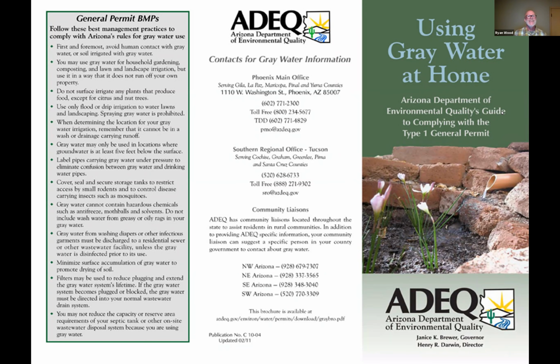So definitely, gray water may only be used in locations where groundwater is at least 5 feet below the surface. So here in the metro area, that's not a problem as far as the water table, but definitely out in the Buckeye area, if you're out in that, check to see where your ground table is. If it's less than 5 feet, then that's your water table, then you can't use the gray water.